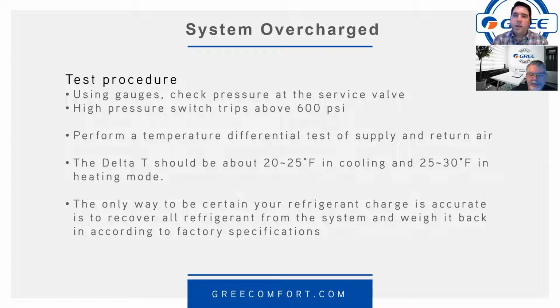I had one the other day that was a low pressure code. No, the end result was low pressure, but the code was reduced frequency for low pressure. So it reduces frequency of the compressor and adjusts the EVs to try to continue running, even though it doesn't have the proper charge that it needs to continue doing the job that it needs to do. So yeah, pretty amazing.